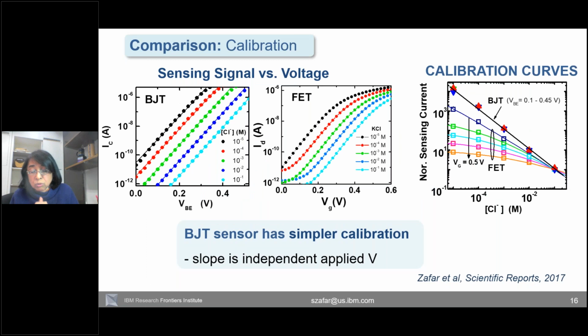First we look at the calibration, which is critical for getting clinical quality data. First, I'm going to show you signal as a function of applied voltage. IC is the signal, the collector current, on the y-axis for both cases. Here is the data for the BJT sensors, measured at different concentrations of chloride. As the chloride concentration increases, the curves shift towards the right. For the FET we see the same thing, but you notice the shape of the curves is different. For the BJT, the current rises exponentially, whereas here they saturate. This difference has a significant impact on sensitivity, calibration and resolution, as I will show you next.